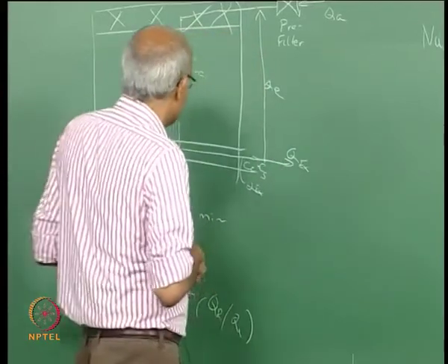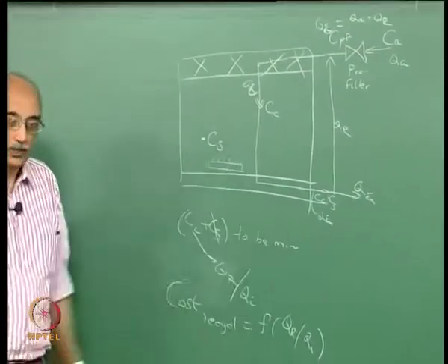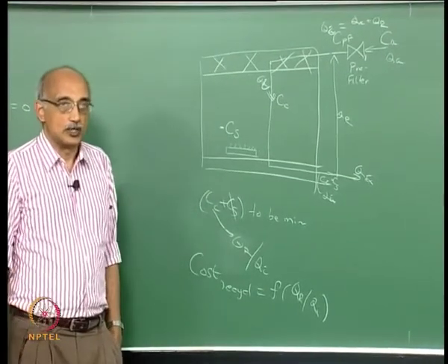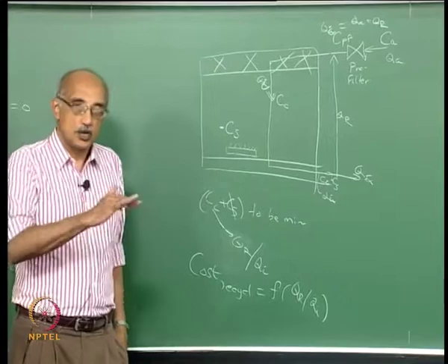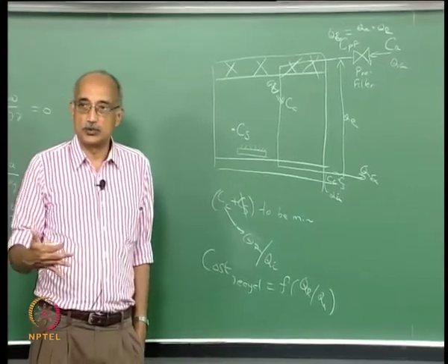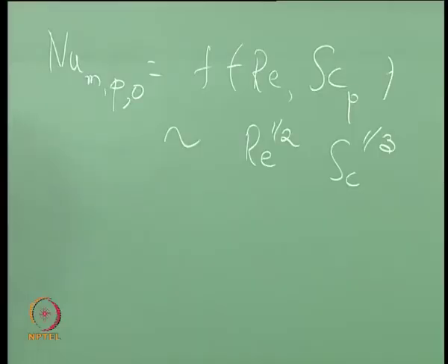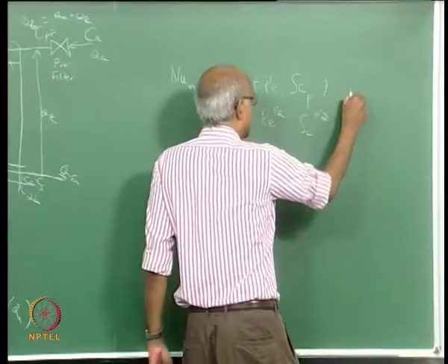So if you look at forces that deliver particles to surfaces inside a clean room, electrostatic forces are probably number one. I mean, in addition to the normal mechanisms of convection and diffusion and so on, which are accounted for in the Nusselt number, but you remember that we have to then multiply this with an F correction.